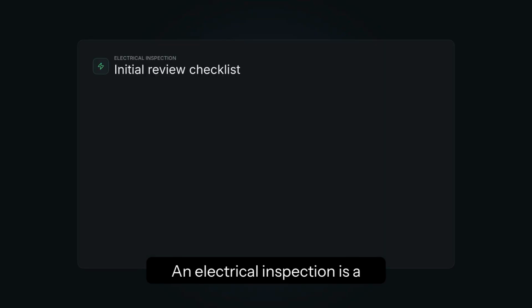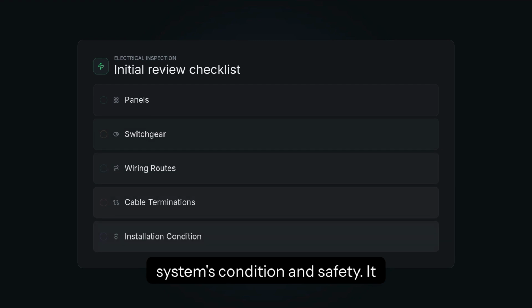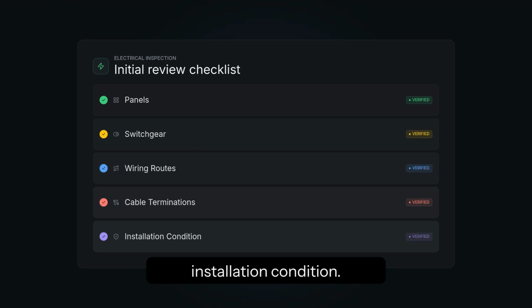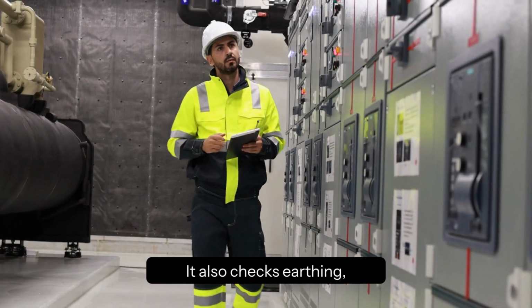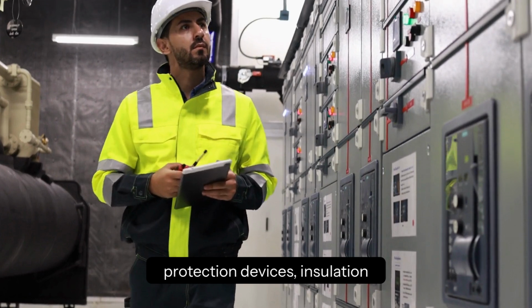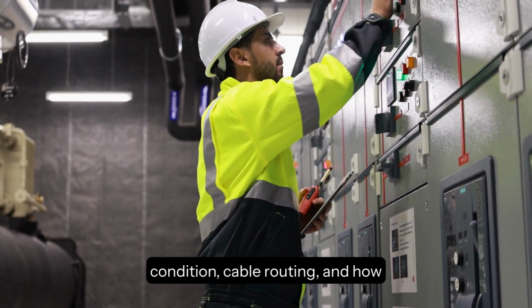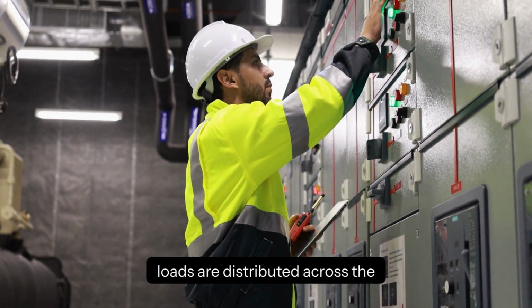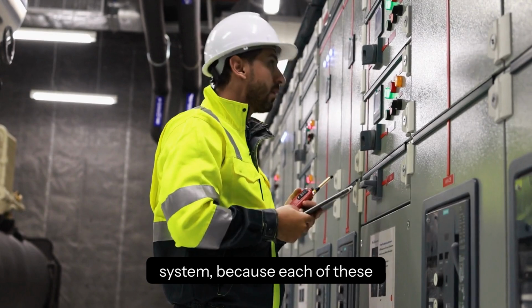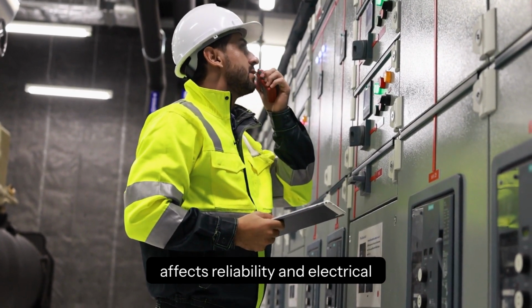An electrical inspection is a technical review of the electrical system's condition and safety. It typically starts with panels, switchgear, wiring routes, cable terminations, and overall installation condition. It also checks earthing, protection devices, insulation condition, cable routing, and how loads are distributed across the system, because each of these affects reliability and electrical risk.